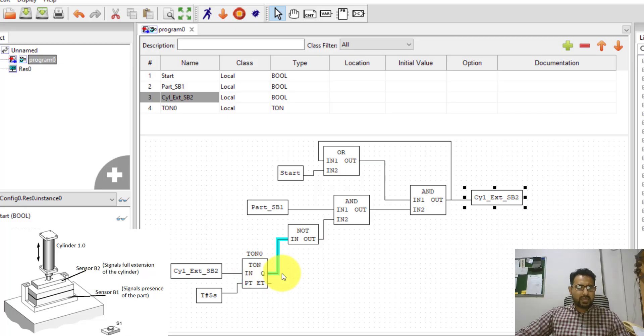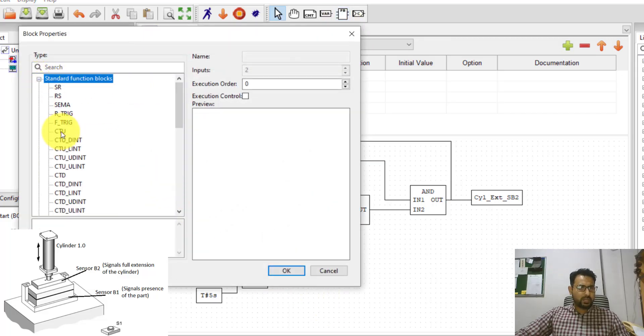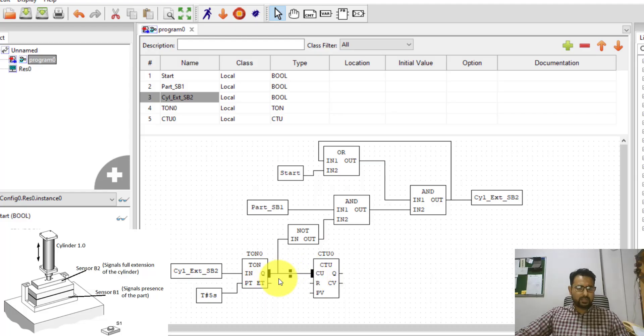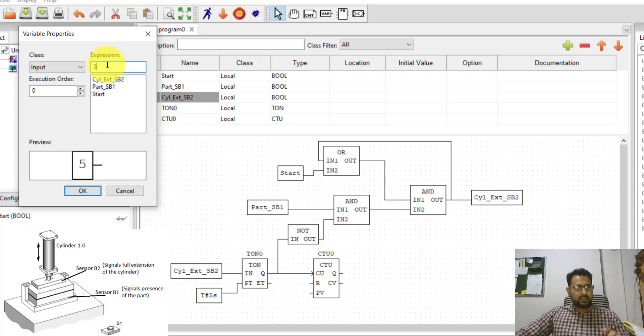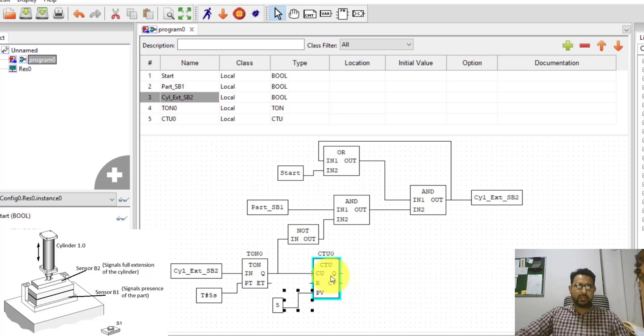When the timer is done timing, I also want to count 1. I need a counter, so I'll insert a counter function block. I connect the counter's CU input directly to the timer's Q (done) pin — whenever the timer is done, the counter counts 1. I set a preset value of 5 by creating a constant with value 5, attached to the counter's PV pin. The counter counts to 5, and then its Q pin goes high.